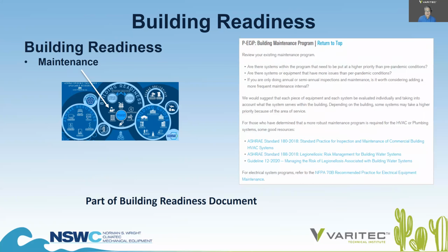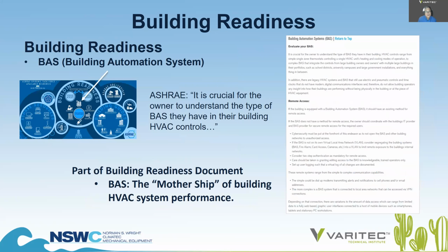is always operational in accordance to design standards, to make sure that the amount of air is necessarily being delivered to the space, the amount of ventilation air is being delivered to the space, and purge cycles are properly scheduled and occurring to evacuate pathogen concentrations that build up during the occupied hours. And then there's the building automation system section.